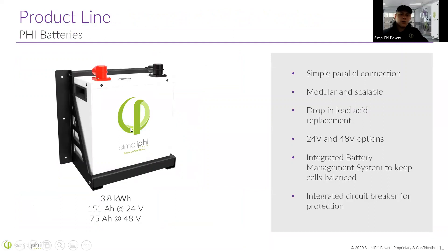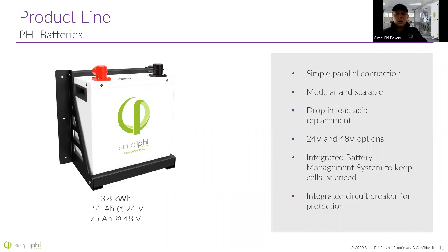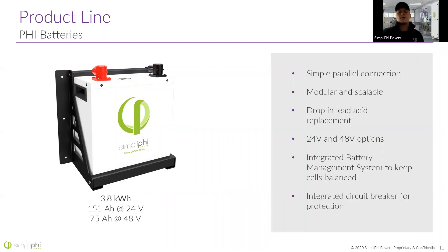We make a 3.8 kilowatt-hour battery that comes in both 24 and 48 volts. It is a parallel connection only — do not buy a 24-volt battery thinking you're going to series-connect them into a 48-volt bank; just buy the 48-volt battery and connect them in parallel. These are really infinitely scalable. In a mobile application you're not going to need 100 batteries, but in a residential application this battery has no limitation as to how many you can parallel — we've seen systems of over 100 batteries in one bank.